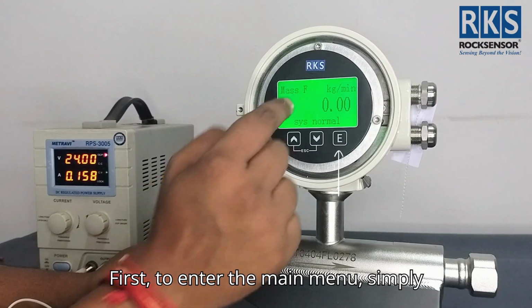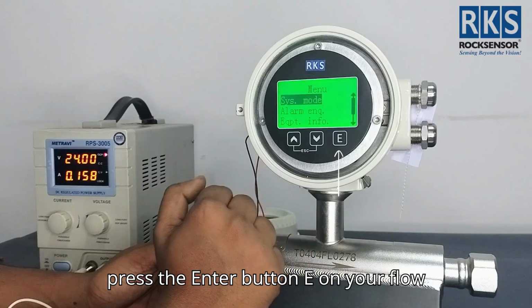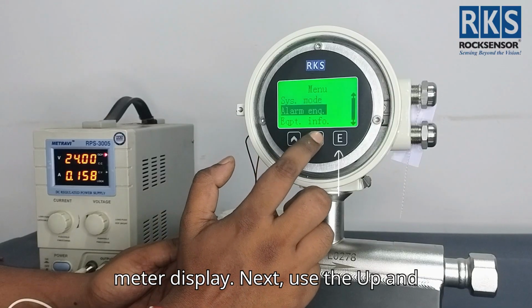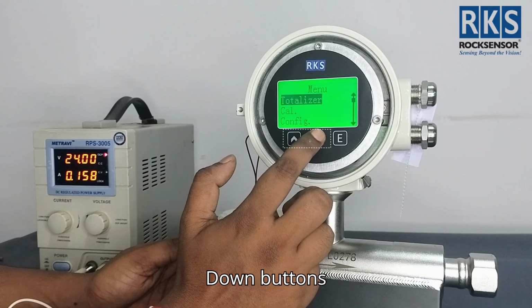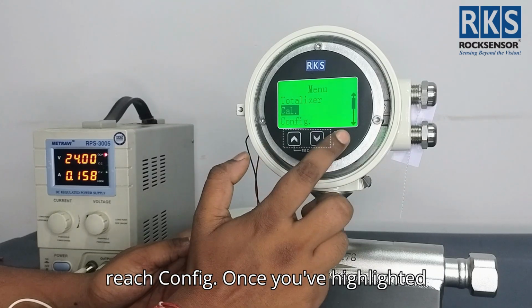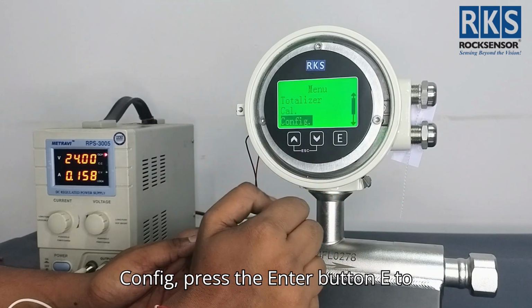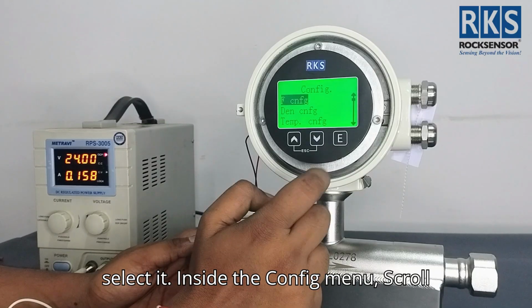First, to enter the main menu, simply press the Enter button, E, on your Flowmeter display. Next, use the up and down buttons to scroll through the options until you reach Config. Once you've highlighted Config, press the Enter button, E, to select it.